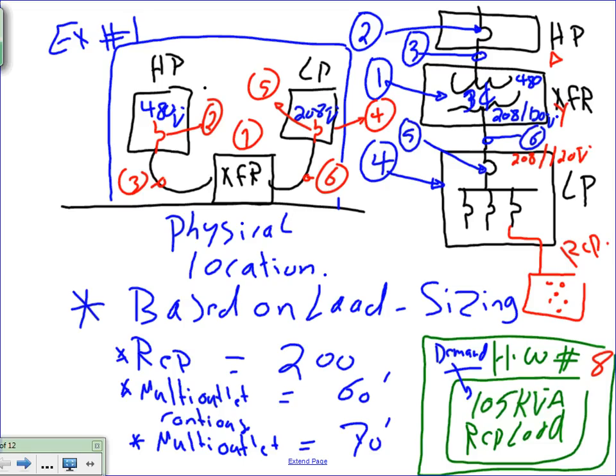Can I get you guys to understand? This is the first page. Right to the first page. It's at the top, the upper left-hand corner. In the first page, where it says homework number 6, please change it to 8. And it's a 105 kVA receptacle load, and I need you to do these 5 things. Can I have your attention for 1 second? I do not want you to derate the 105. Don't take the first 10. It's already done. This is all demand. Just do the 5 steps.